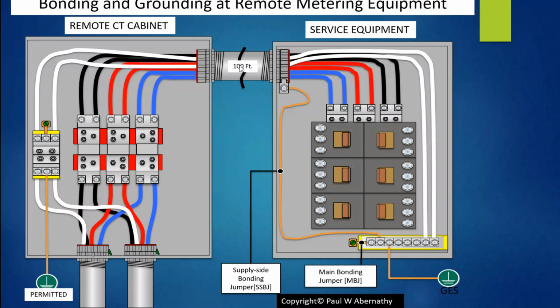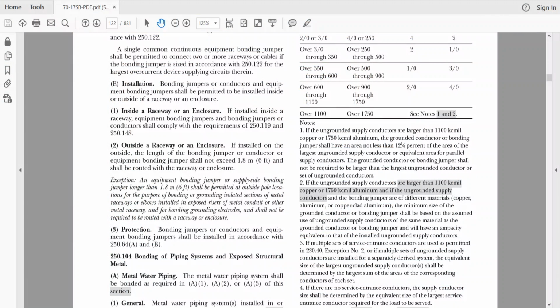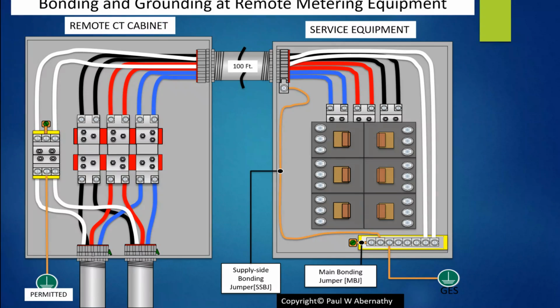All right. Now, this raceway right here, obviously, since I'm only running one, I have 3 sets here. So I take set A. This would be 500, 500. So it'd be 1,000 kcmil. That's the size of the conductors that are in this raceway feeding it. I size this one here based on 250.102C1 to determine what size that bonding jumper needs to be. So in this case, since we said it was 1,000 kcmil, we're going to go back to the NEC and we say, okay, it's 1,000 kcmil, so it's over 600 through 1,100. So that would be a 2-aught right here. A 2-aught supply side bonding jumper. All right, let's go back to the PowerPoint.